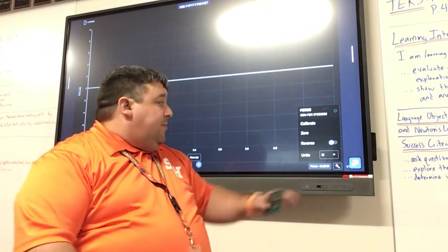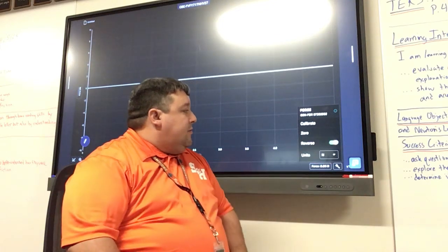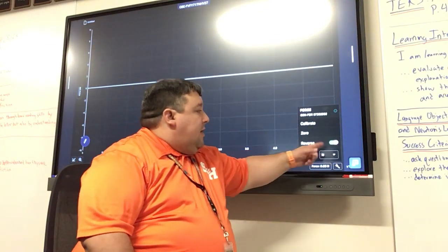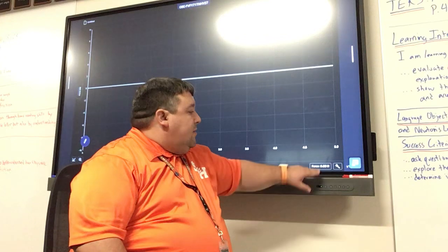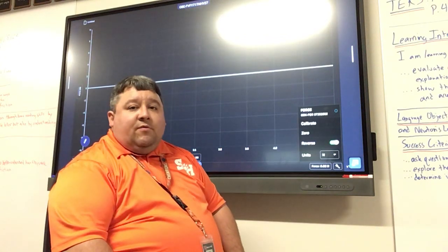The last step, one of the two force sensors, you do need to reverse it. You just tap on this little reverse thing here to do that. I do need to zero this. Let me zero it real quick. And then I tap it again. And then, again, there's my reverse.